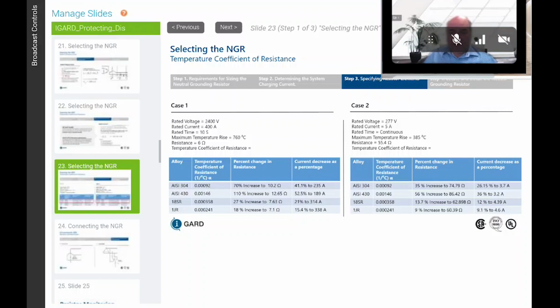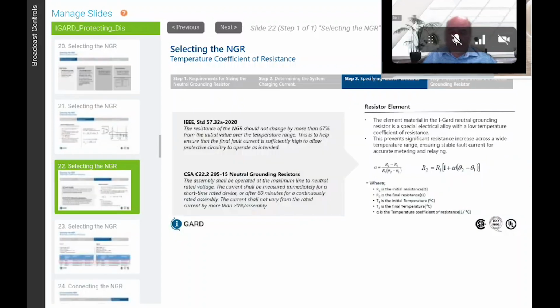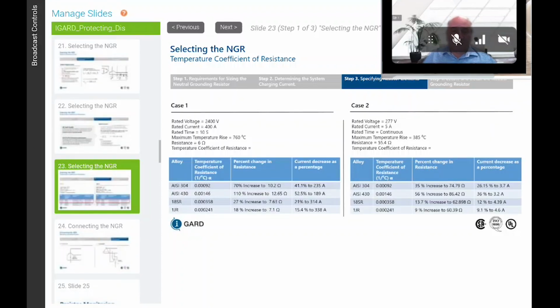For a high resistance ground in the system, 5 amp, 277 volts, 55.4 ohms, same materials, same temperature coefficient of resistance, we see a 35% increase in resistance, and a 56% increase of resistance. The only difference here is we've lowered the temperature for this formula. Theta 2 minus theta 1 is 385 as opposed to 760. So we have less temperature resistance change.